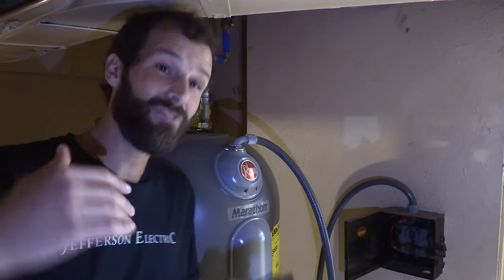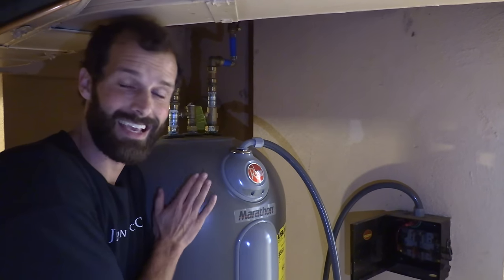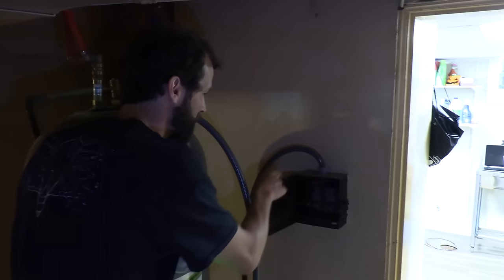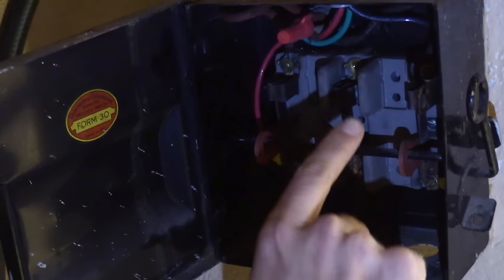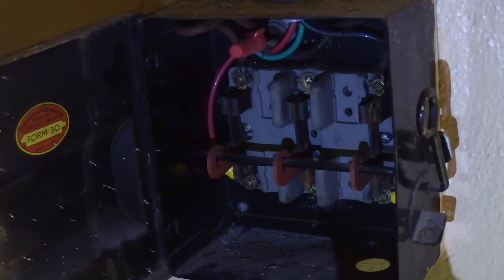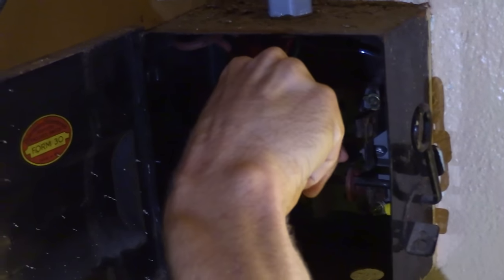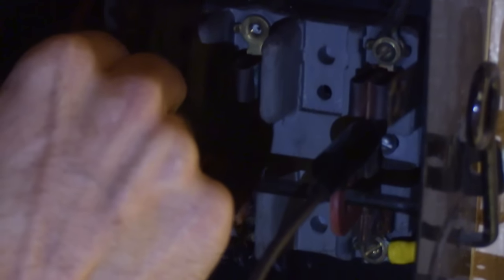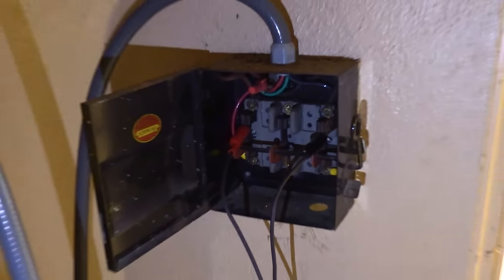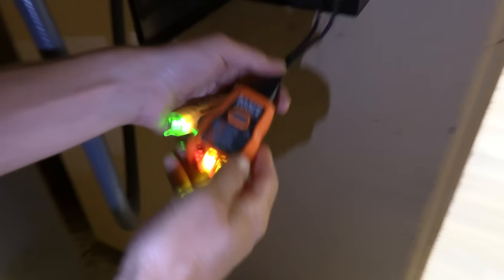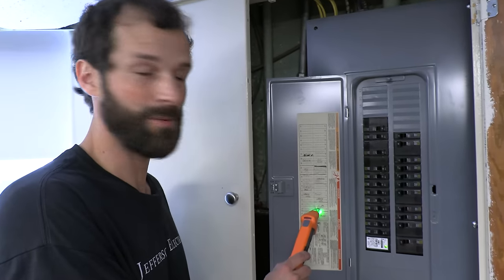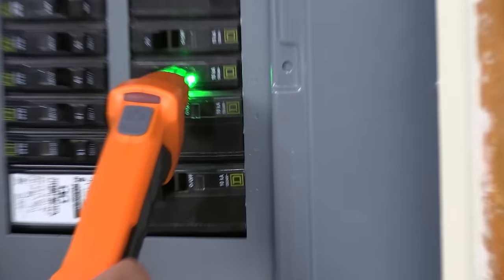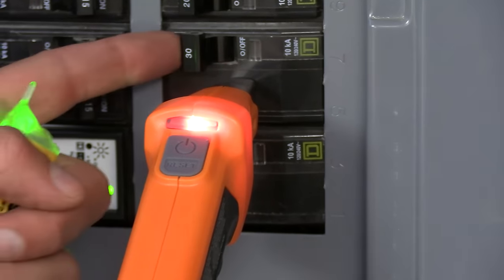So there are at least four or five different types of water heaters. In this case, I've got an all-electric tank-style water heater. And I'm going to test at this archaic disconnect that's sitting on the wall here. So I'm going to take my alligator clips. I'm going to look at the incoming or outgoing wire. There's plenty of opportunity for shock hazard here. So move with caution. And I'm going to clip right on to the electrical components. I can't even quite see that. There I am. I'm expecting that this tank-style water heater is going to be a 2-pole 30-amp breaker. But I do have multiple 2-pole 30s. So let's see what we get. We've got the H2O label here. I'm going to just trace right down here. Okay. That looks to be it. Let's try it.